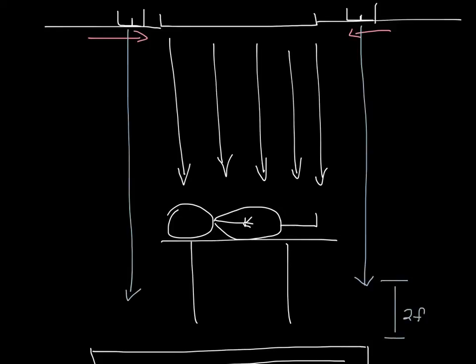You want to select the air curtain so that you're around 50 feet per minute about two foot above the floor.